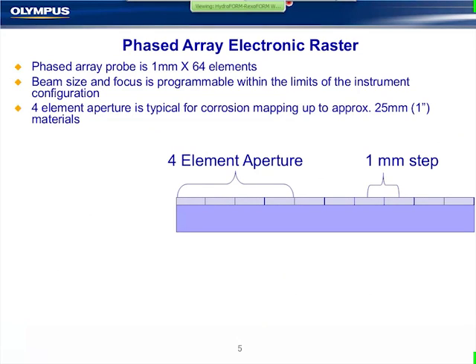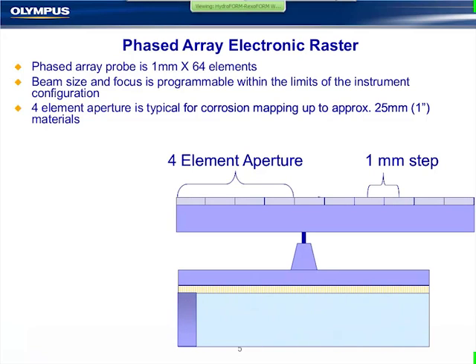uses a 4-element aperture. So most of the probes that we're using are 0.6 or 1 millimeter pitch. So the large 1 millimeter pitch footprint using 4 elements gives us the beam quality of approximately a 4 millimeter conventional probe. We step through the probe in apertures like you see here. So any one A scan is sharing several elements. We're essentially replacing the mechanical raster scan with an electrical scan in one of the axes. This simplifies the mechanics. It allows us to use push scanners and small encoders in one axis and still acquire high precision data points.